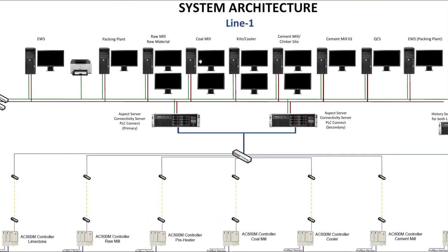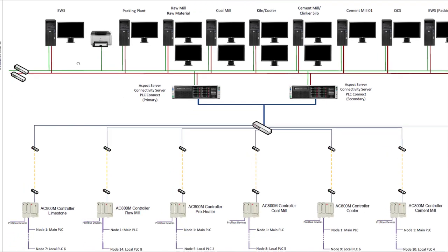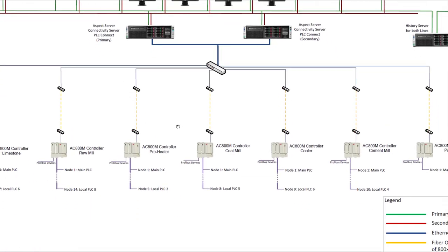The engineering station holds all the PLC programs. We can monitor the PLC programs from this engineering workstation, and we can download the PLC program from the engineering workstation to the specific PLCs. If we want to modify a PLC program or make any modifications according to the process requirement, we download the program to the PLC through the engineering workstation. We can also upload and read the program from the PLCs through the engineering workstation.